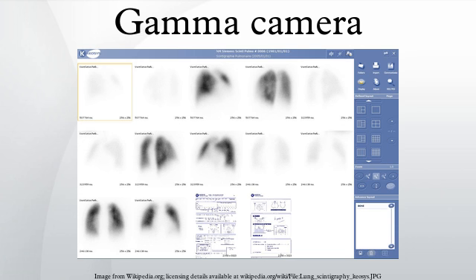However, the collimator is also one of the sources of blurring within the image. Lead does not totally attenuate incident gamma photons; there can be some crosstalk between holes. Unlike a lens, as used in visible light cameras, the collimator attenuates most incident photons and thus greatly limits the sensitivity of the camera system. Large amounts of radiation must be present so as to provide enough exposure for the camera system to detect sufficient scintillation dots to form a picture.